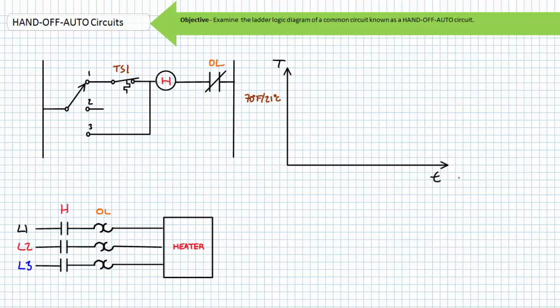The switch in position one allows the temperature switch to automatically govern the heating process. If the temperature switch senses temperatures below 70 degrees Fahrenheit or 21 degrees Celsius, it is in its deactivated state and the heater contactor coil would be energized and the heater would come on.